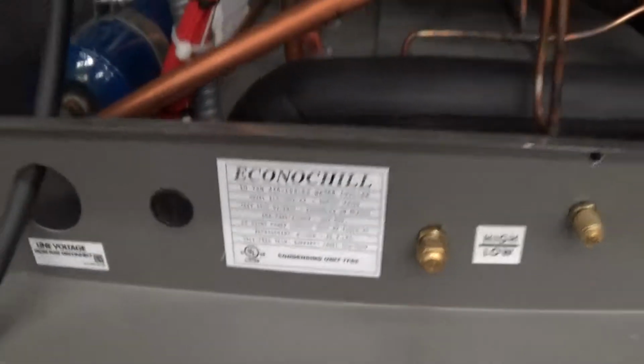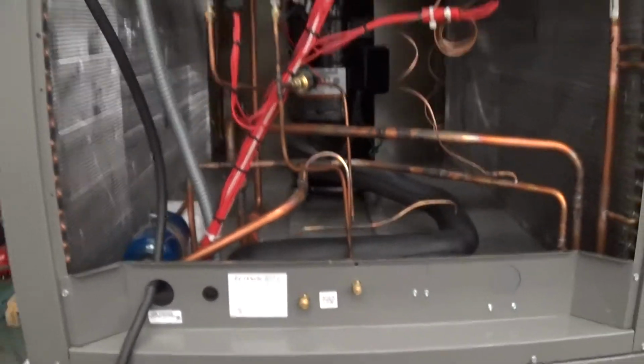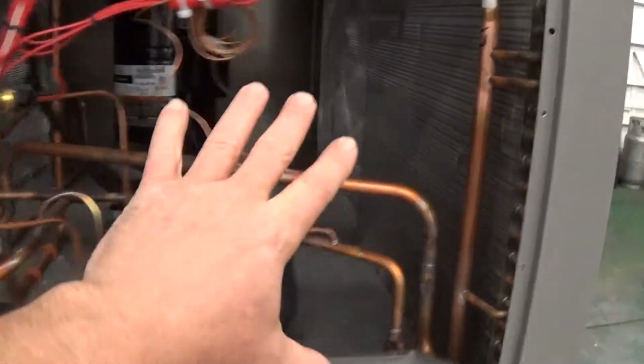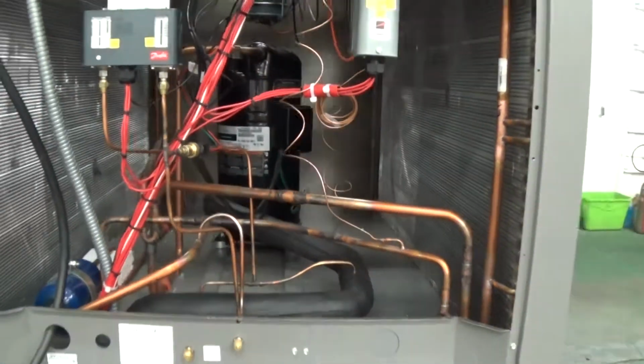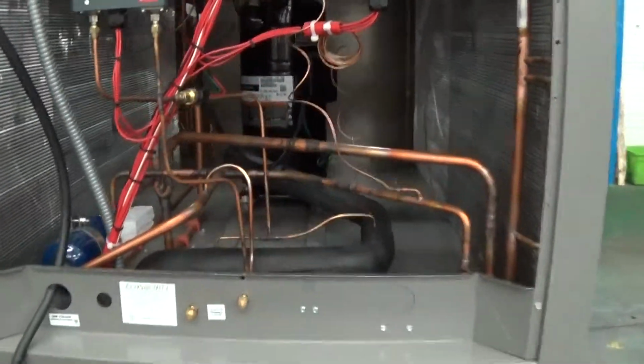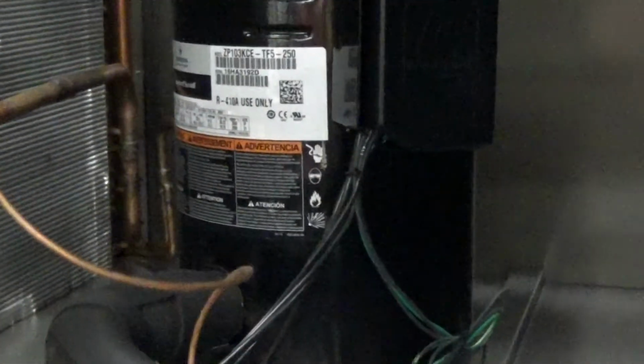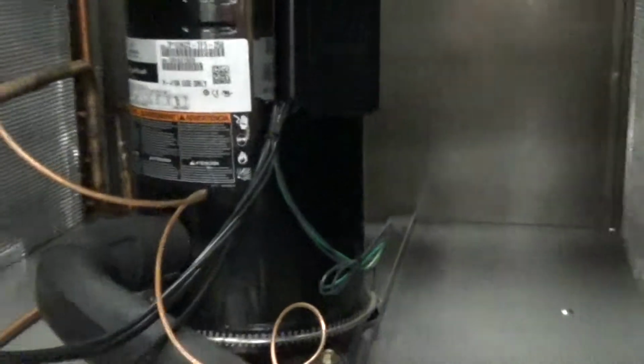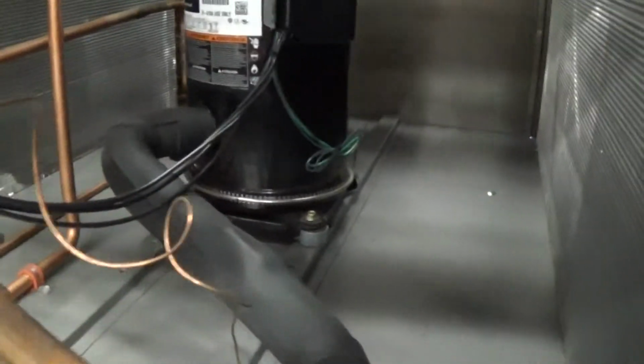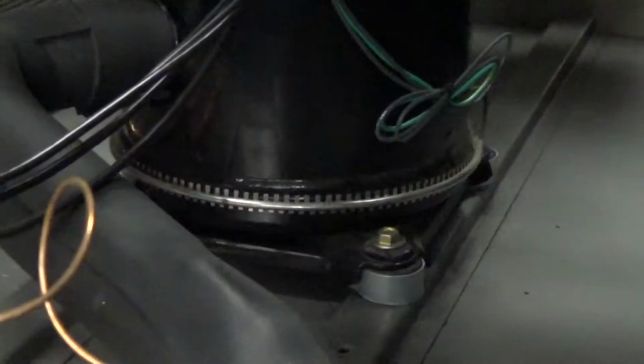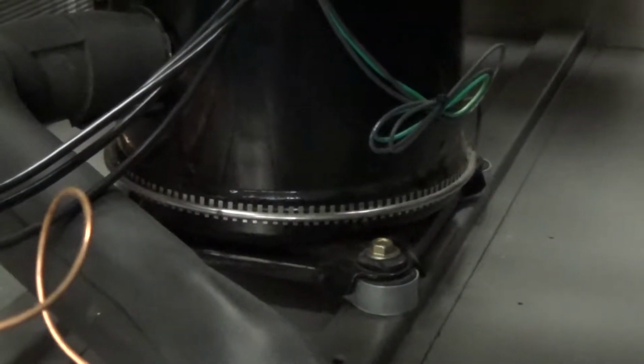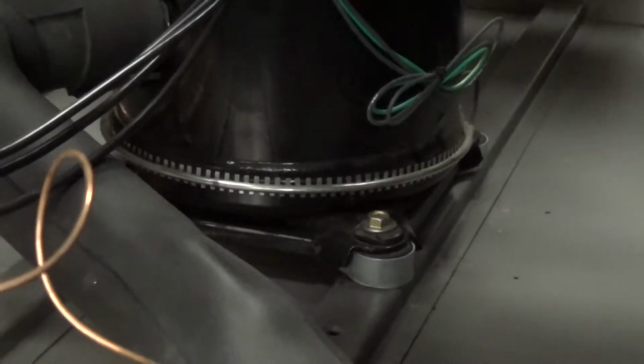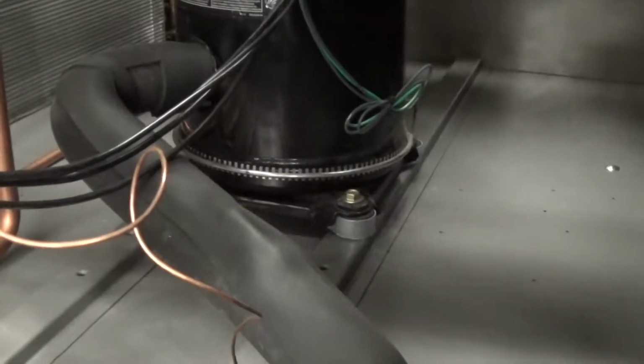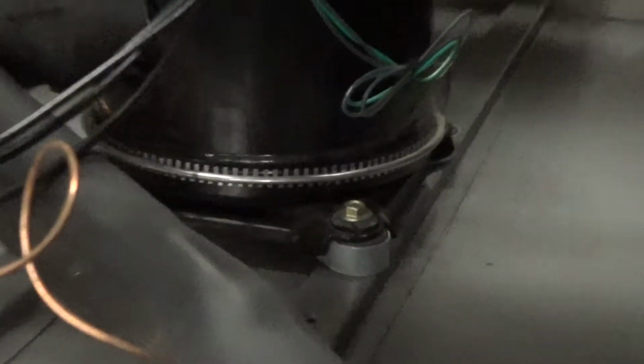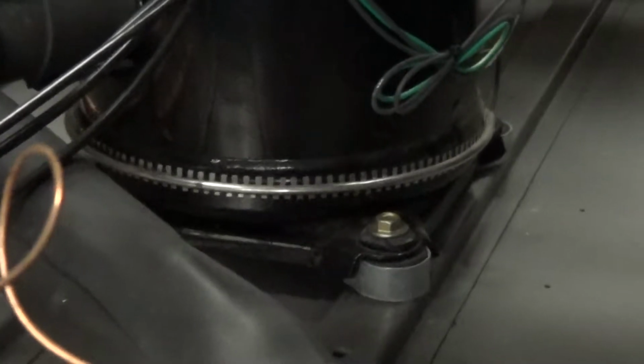We're going to have the covers off for most of the test, except for this one cover here. This side cover has to be on there for appropriate airflow through the condenser. We have our 10 horsepower Copeland scroll compressor, single one, R410A, inside the main body of the unit. It does have a crankcase heater on there. When you first put power to the unit, it's good to keep that on for at least 12 hours or so. That keeps the refrigerant warm, and it's ideal in cold weather solutions also, or situations.